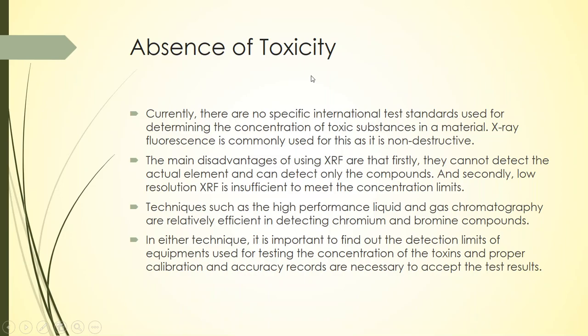So how do I test, right? Whether it is 0.1 weight percentage or 0.15 weight percentage. Even 0.15 would probably not be acceptable. 0.09 would be acceptable, but not 0.15, right? So how do I know? How do I test? Unfortunately, there are no international standard tests, you do not have any gold standard tests saying that, okay, if my device passes this particular test, then I'm clear, I'm okay to sell my device in the European Union.